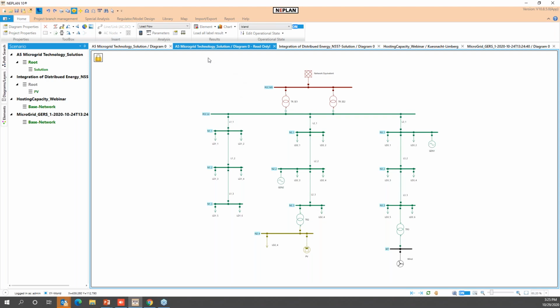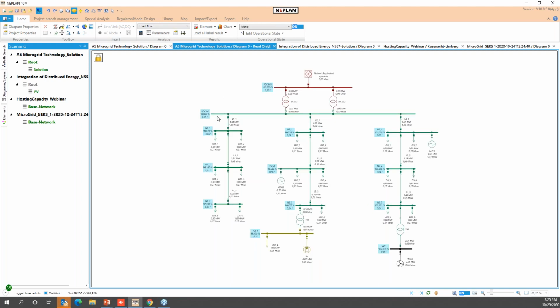But the system is now disconnected. If we run the same case, quickly here, we can see that, again, the voltages are within the corresponding margins, plus or minus 5%. We don't have any transfer from the national system. It's 0 megawatts, 0 megavars. What about the voltages? Again, good enough. And the losses? The losses became 0.17.